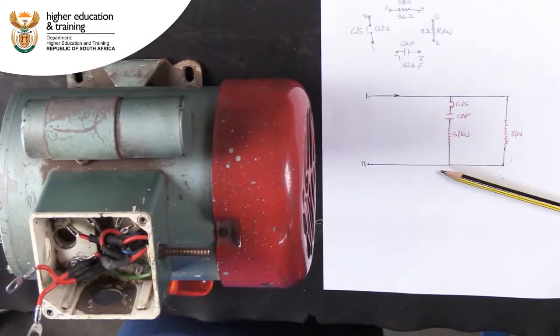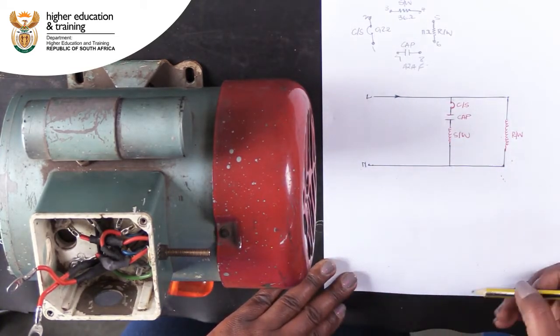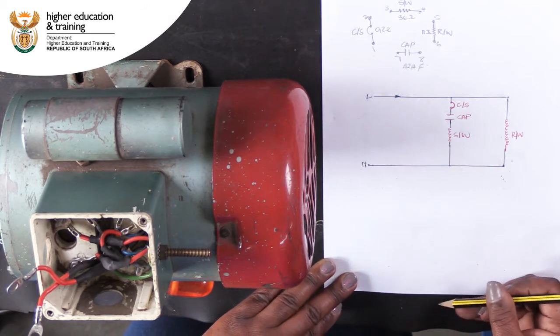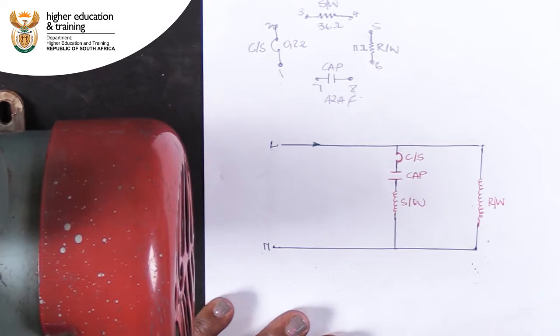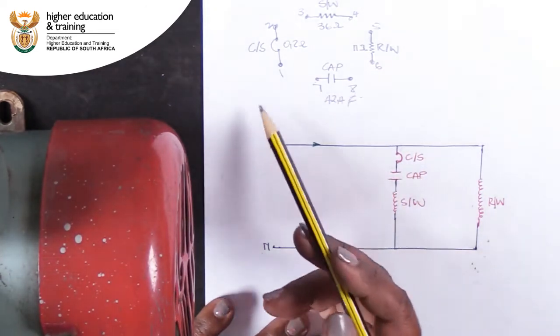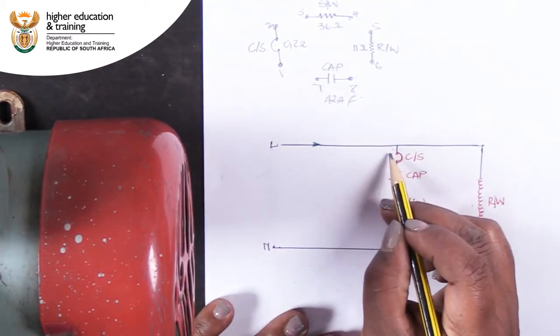Now that we have a schematic, we can use it to determine how to connect this motor to a supply. The first thing to do is to number the posts on our schematic. We know that the centrifugal switch is between points 1 and 2. We indicate these on our schematic.